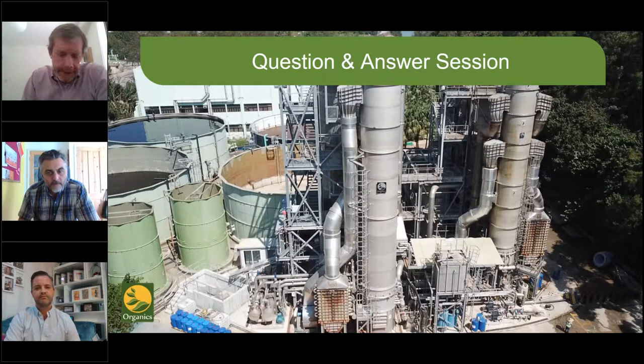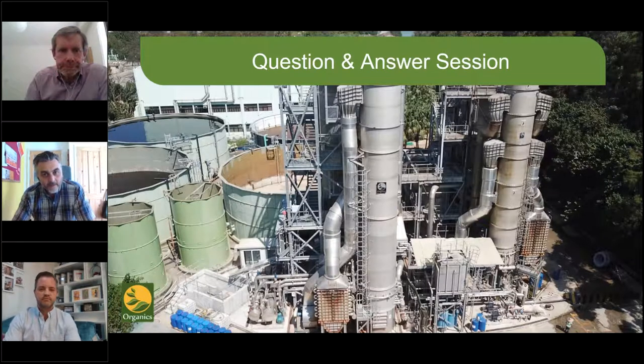Okay. Great, thanks. Another question is, how much aqueous ammonia is possible to recover from a typical thermal hydrolysis plant? I guess that would be something like a Cambi system, presumably with a concentration of around 1,500 to maybe 2,500 milligrams per litre in the sludge liquor. Well, that's going to depend very much on the flow rate. But if it's coming in at 2,000, you could recover up to 1,900 milligrams per litre of ammonia, and then multiply that by your number of litres, and that's your potential per day, and you can come up with the potential ammonia recovery from that product. So it really is flow dependent.